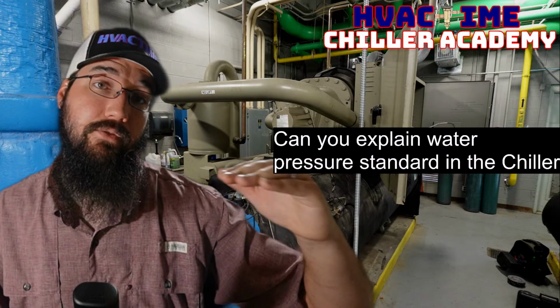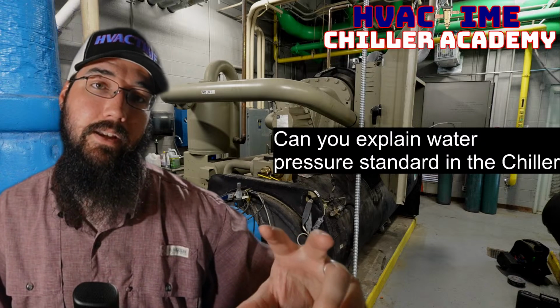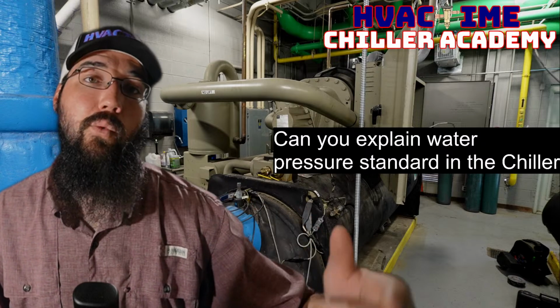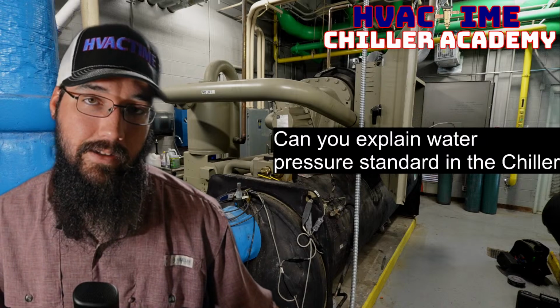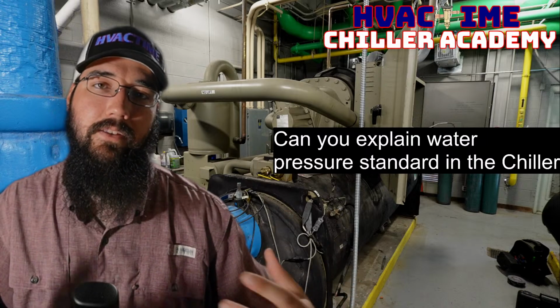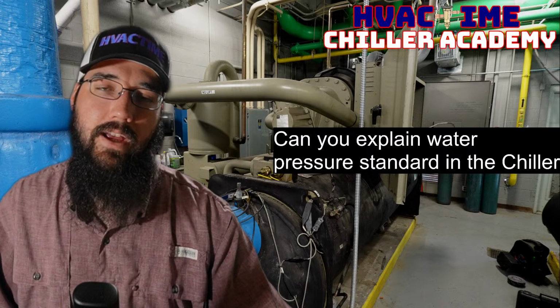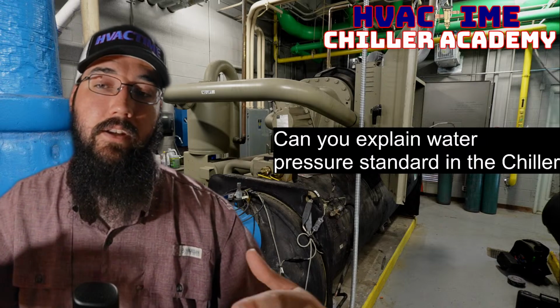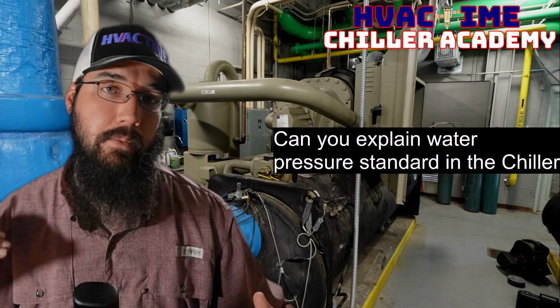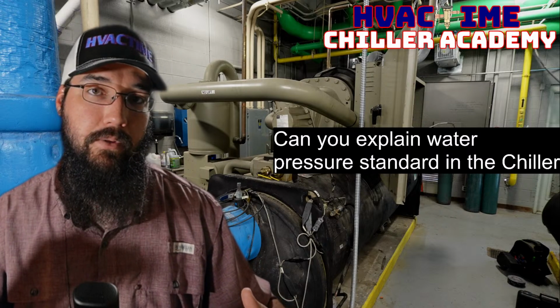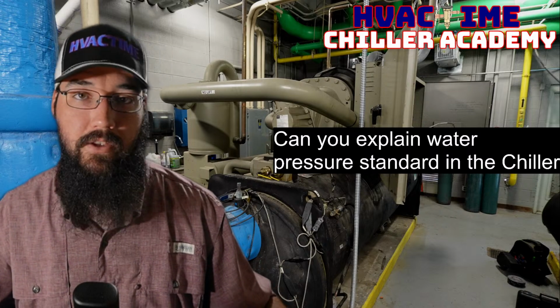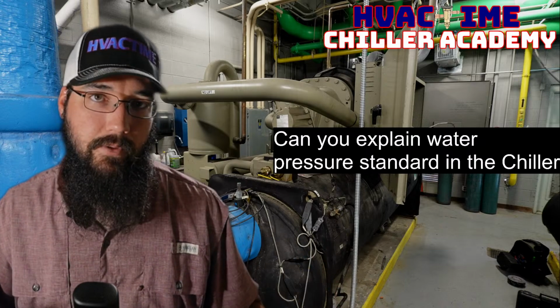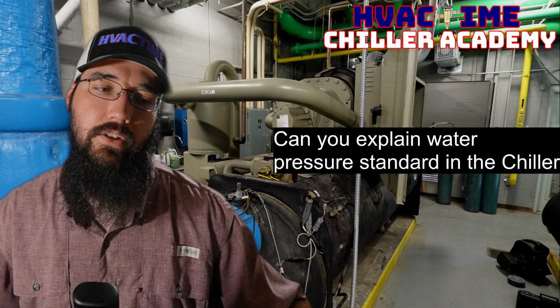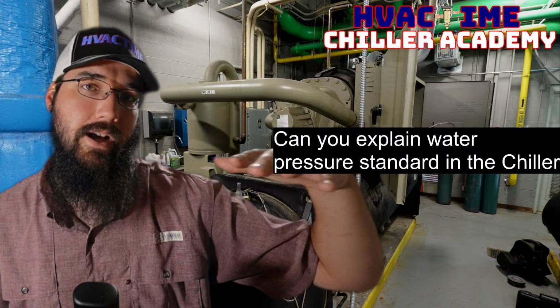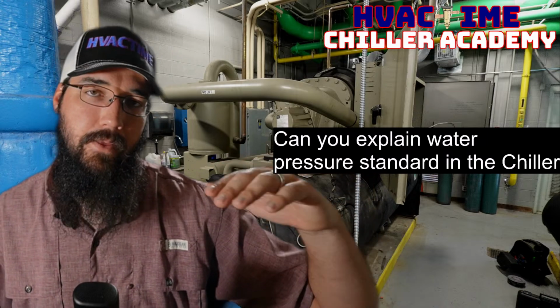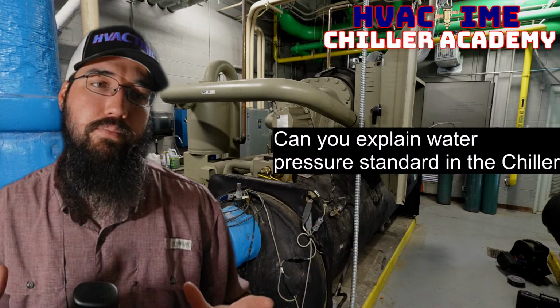And I like to have at the very top of my loop about 8 to 10 psi of positive pressure with the system online and running. When I have that, for me, that's a gauge to say I've got adequate water. Now, it doesn't matter if my pump was on the roof, halfway down the building, or down in the basement. That is irrelevant. What matters is what the pressure is to the actual height of the loop. That will determine what our actual loop pressure is going to be.